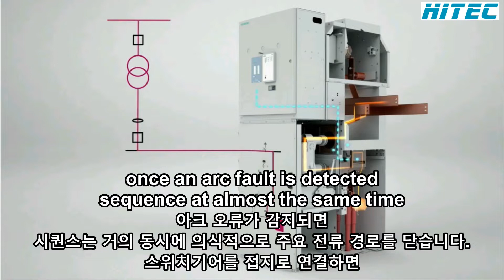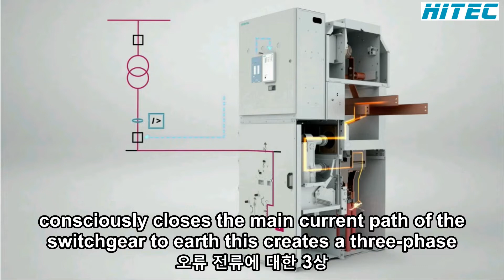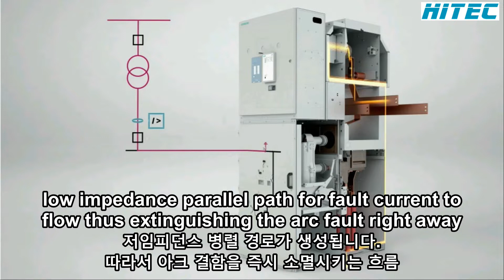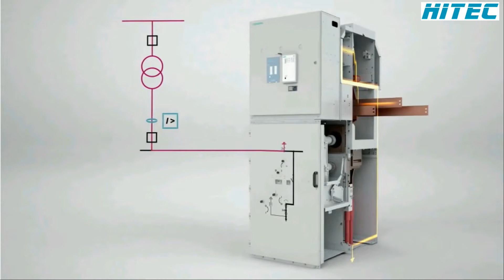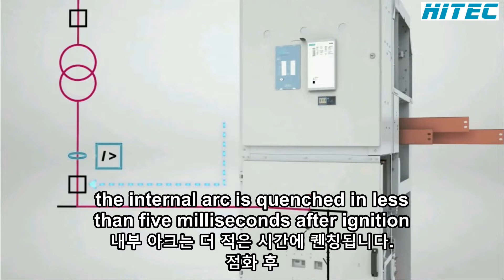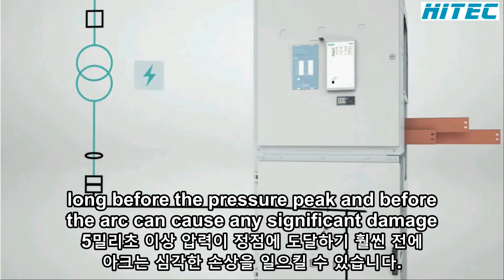Once an arc fault is detected, SIQuench, at almost the same time, consciously closes the main current path of the switchgear to Earth. This creates a three-phase low-impedance parallel path for fault current to flow, thus extinguishing the arc fault right away. The internal arc is quenched in less than 5 milliseconds after ignition, long before the pressure peak and before the arc can cause any significant damage. It minimizes the damage within the switchgear due to reduced arc energy and pressure. Service can be restored rapidly, leading to minimized service outages.